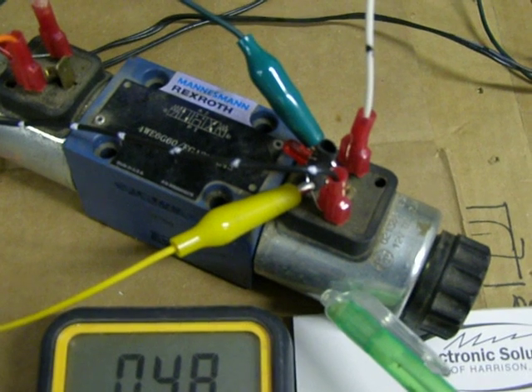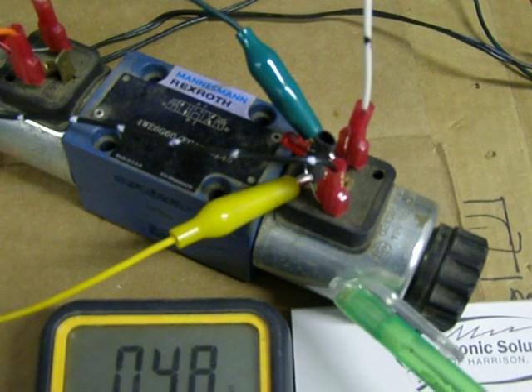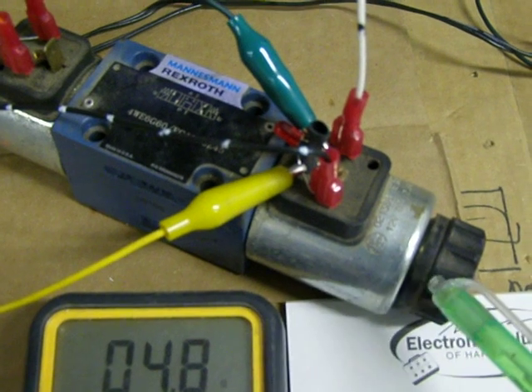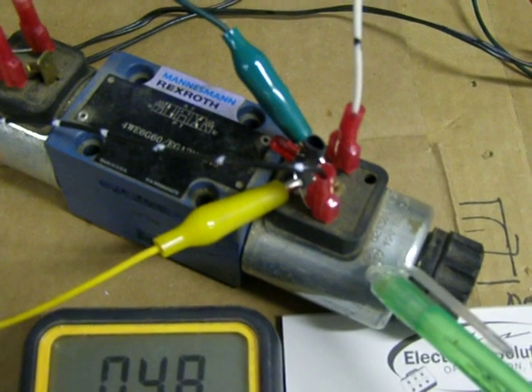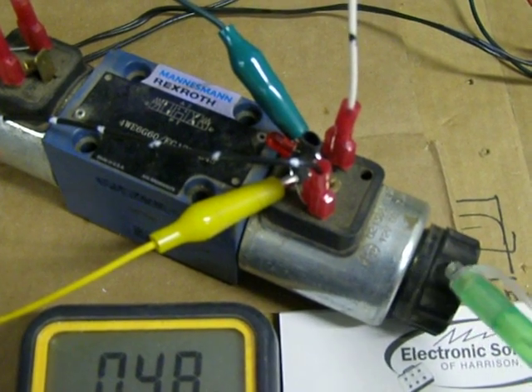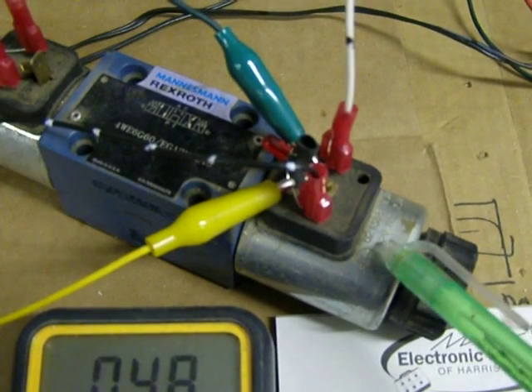Inside of here is a winding of copper wire. It's usually enamel or lacquer plated. These metal ones are pretty decent, but some of the plastic ones, if you overtighten this nut, you'll crush it and then it'll short out in there.